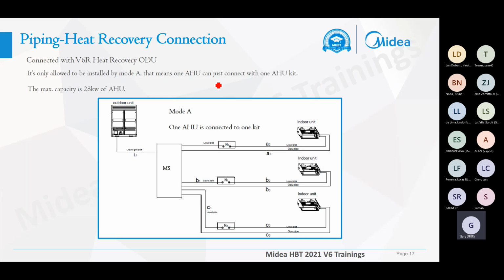And for the V6R, the maximum capacity is 28 kilowatt of AHU. We have measured this several times because this is very important. As the AHU can be up to 28 kilowatt, normally we can only use one kit. In a simple case, connecting to one AHU is enough.